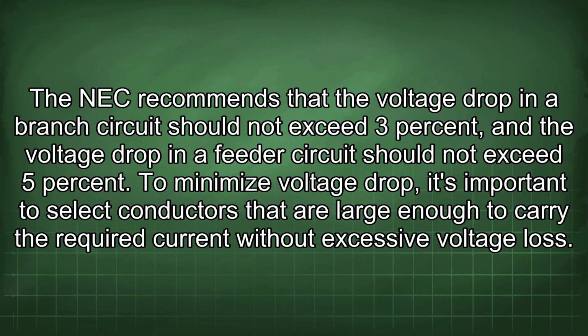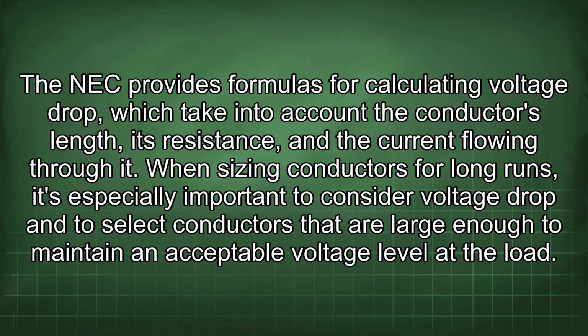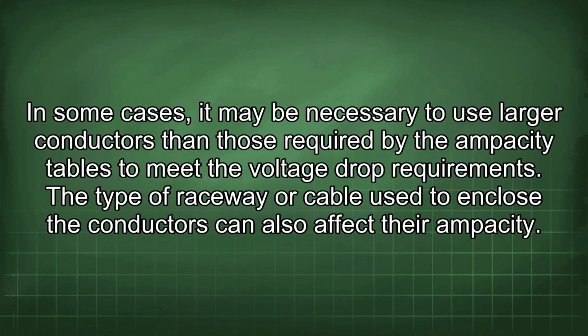To minimize voltage drop, it's important to select conductors that are large enough to carry the required current without excessive voltage loss. The NEC provides formulas for calculating voltage drop, which take into account the conductor's length, its resistance, and the current flowing through it. When sizing conductors for long runs, it's especially important to consider voltage drop and to select conductors that are large enough to maintain an acceptable voltage level at the load. In some cases, it may be necessary to use larger conductors than those required by the ampacity tables to meet the voltage drop requirements.